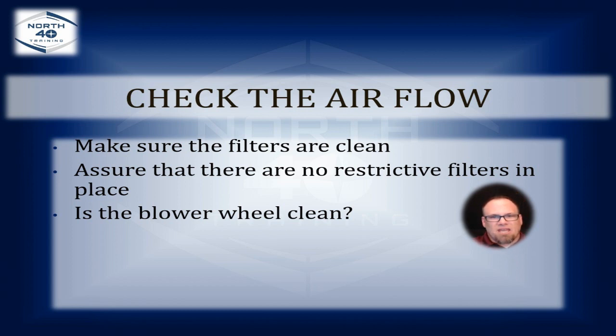And you think about it, 10%, that's a dryer sheet getting stuck in the filter. That's a restricted secondary heat exchanger that rests above the blower wheel. That's the blower wheel itself, those little scoops that have barely a turn on them, getting a little bit stopped up with dust or hair. Those things make a huge difference. And if you've got to dismantle that blower housing, take the motor out of there, take the wheel off the motor and wash it out, and that's going to be the difference for the customer, you've got to take care of that.